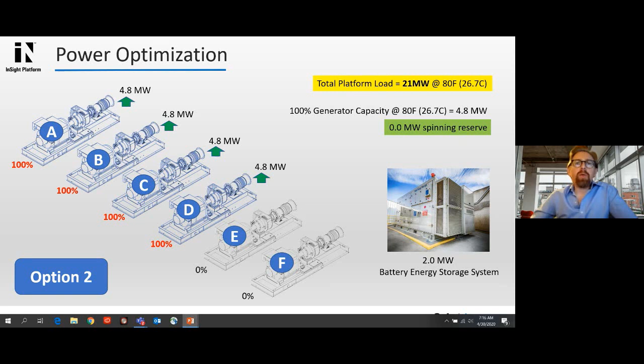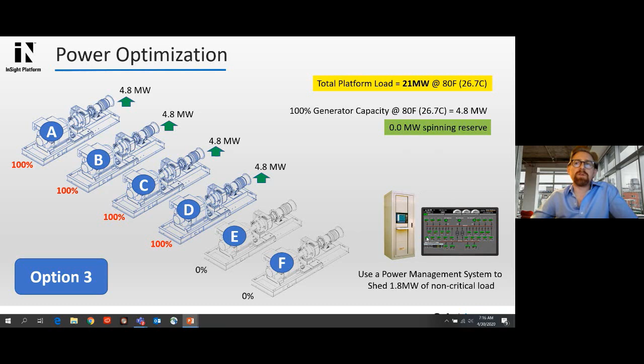The third option we could explore is the use of a power management system to shed non-critical loads. So for most of our customers, they have multiple buses on the platforms, typically a critical and a non-critical bus. The application of a power management system would be to sense what the load is on the platform, and then to close, or rather open up non-essential breakers to bring the load profile back within the capacity of the power generation equipment.